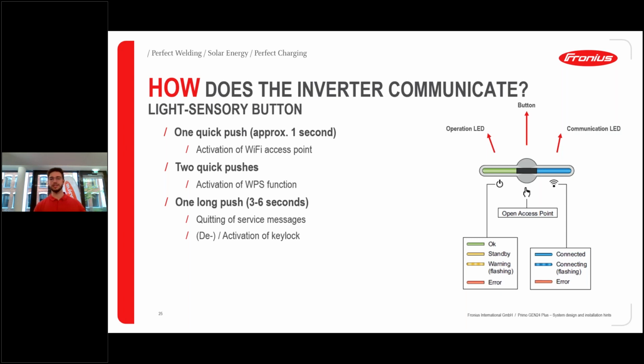So just quickly talking about the 2 LEDs that we can see here. The left LED, which is green on this screen, is the operation LED. It indicates if the inverter is running and what the status of the inverter is, if there is any failure or a standby, something else. And the right LED is the communication LED. So we can see if the access point is opened. It's then blinking blue, and a constant blue light would, for example, mean that it's connected to a Wi-Fi.